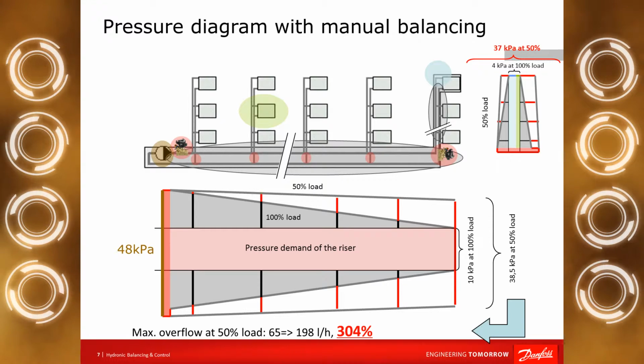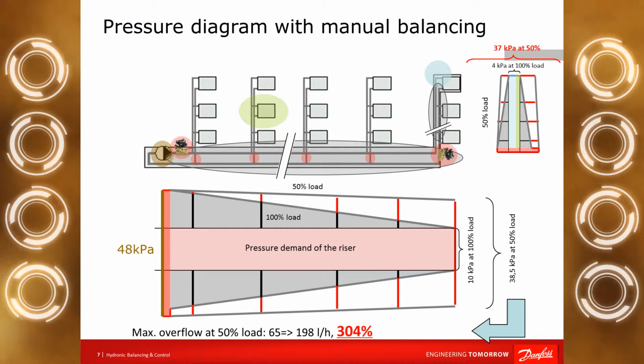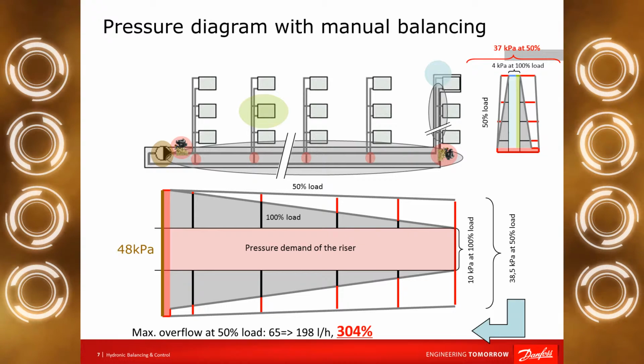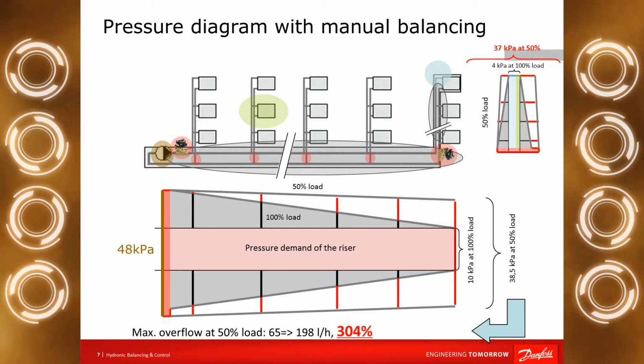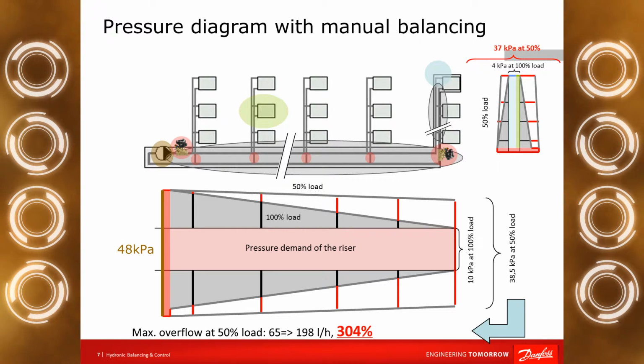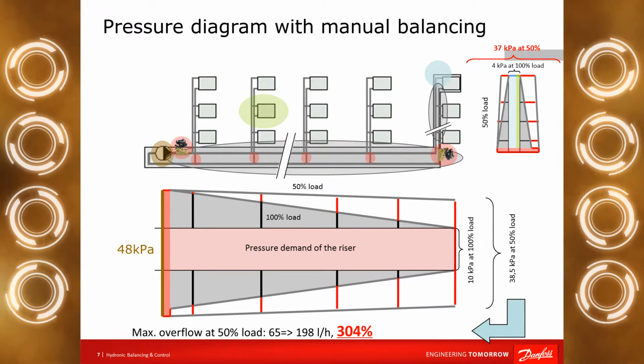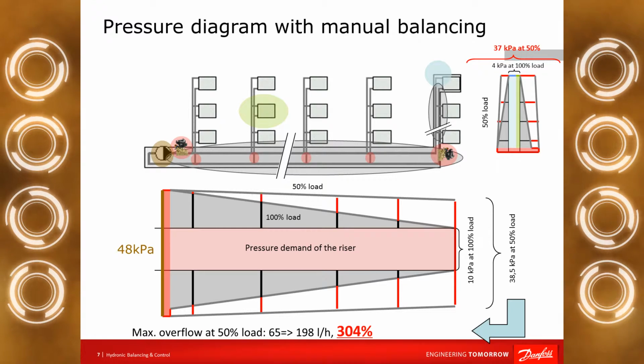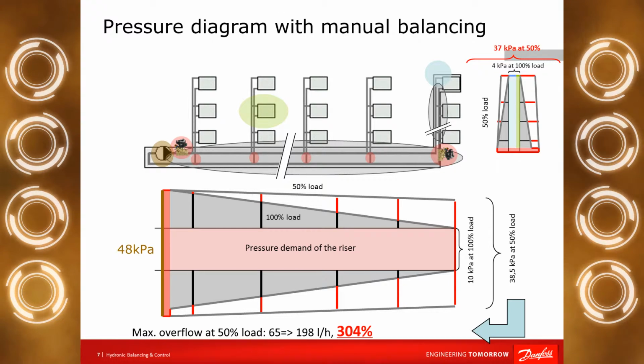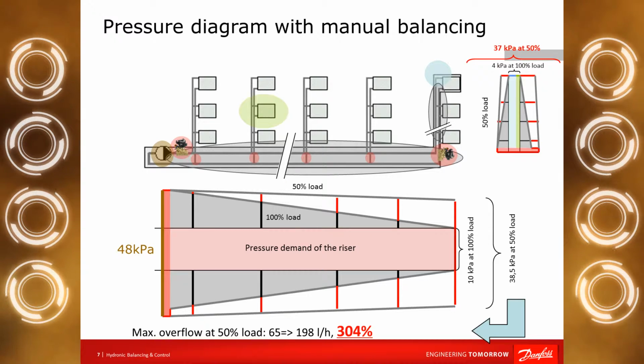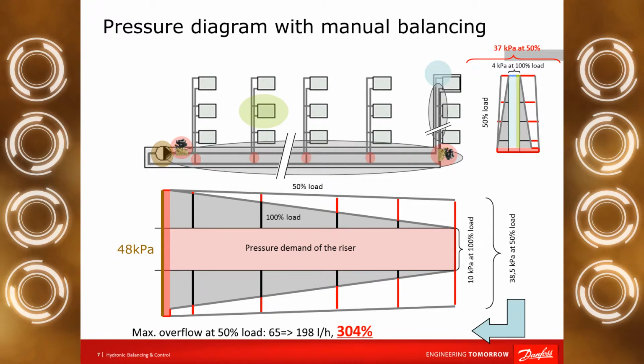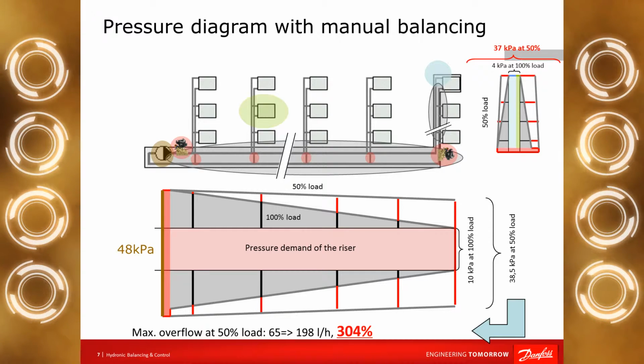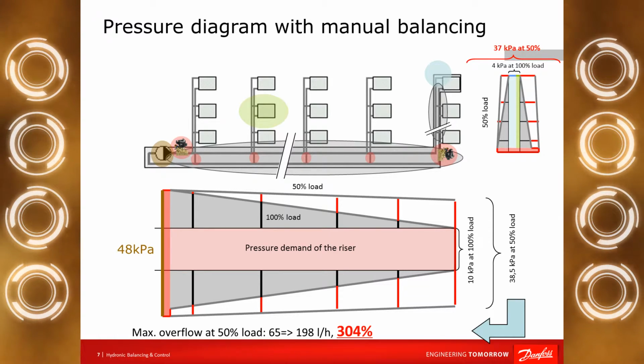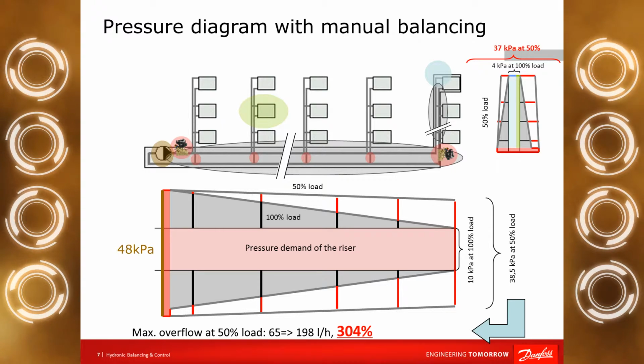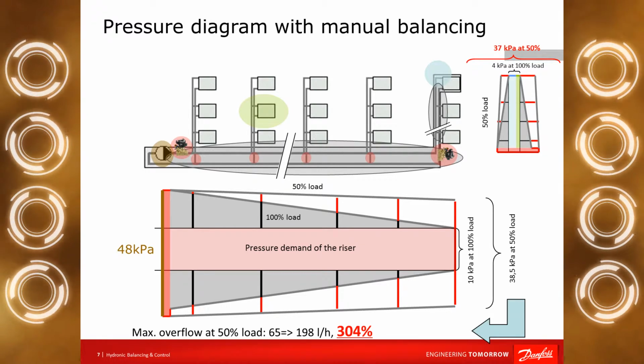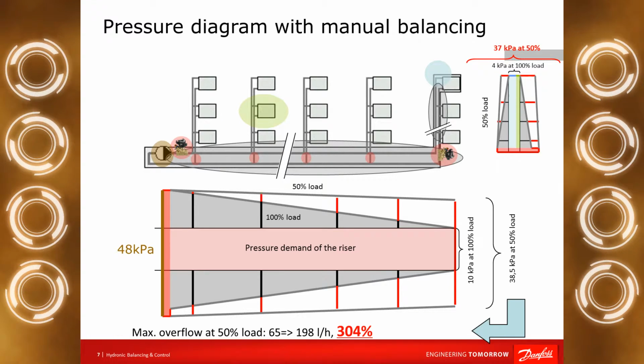You can see with this gray line what is the available pressure on the distribution line and on the riser during the partial load condition. Because of the lower flow rate through the pipes, the pressure drop will be smaller. Therefore, the available pressure on the end of the riser will be dramatically increased, and not only at the end of the riser, at the top of the riser it is increased even more. Here, instead of the originally preset 4 kilopascal, we will have 37 kilopascal. This is a huge overpressure at that point.